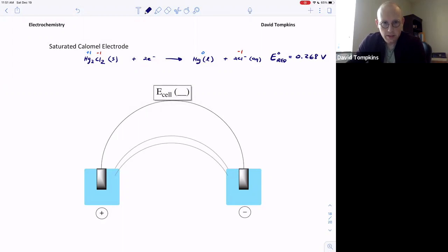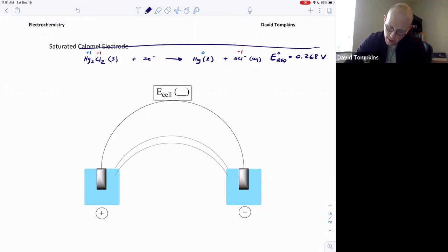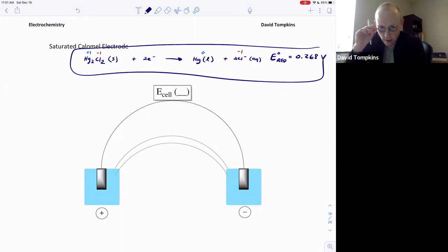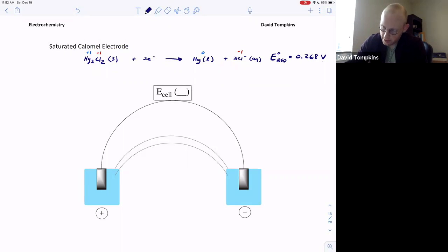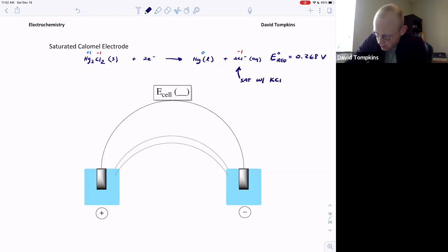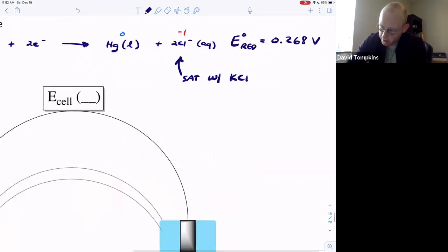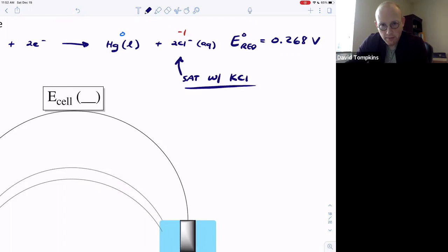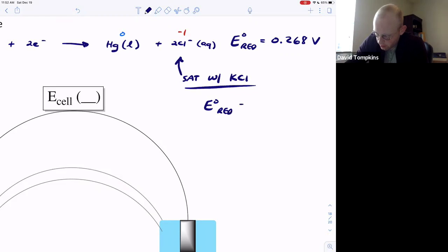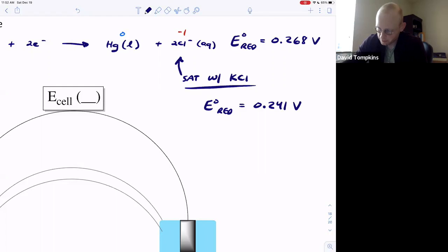Like the silver/silver chloride electrode, we want this half-reaction to be the fixed half-reaction with a fixed potential. We do that by saturating it with potassium chloride, fixing the chloride concentration. When saturated with excess potassium chloride, instead of having a variable chloride concentration, the potential changes to 0.241 volts, and that is the value we use in most calculations.